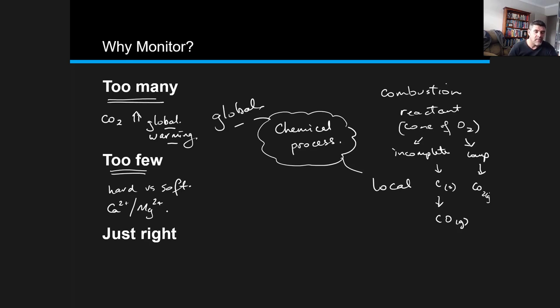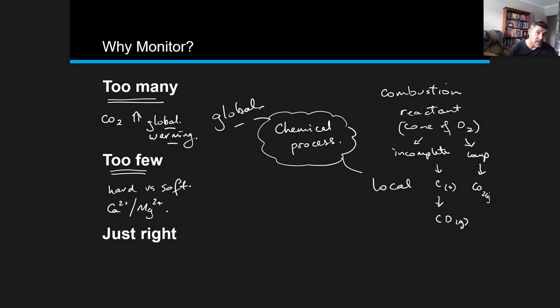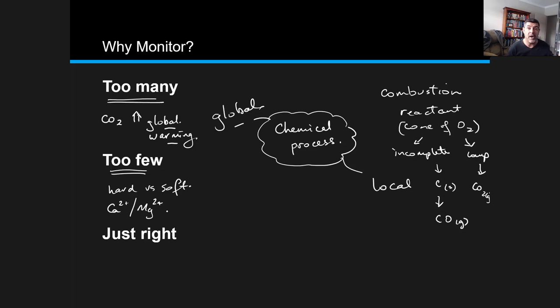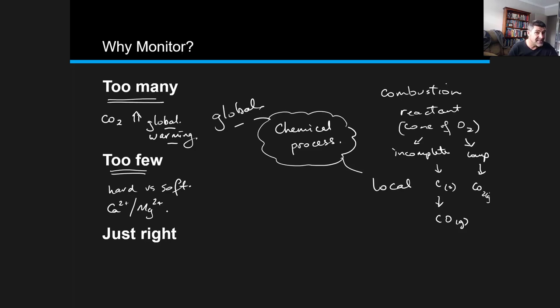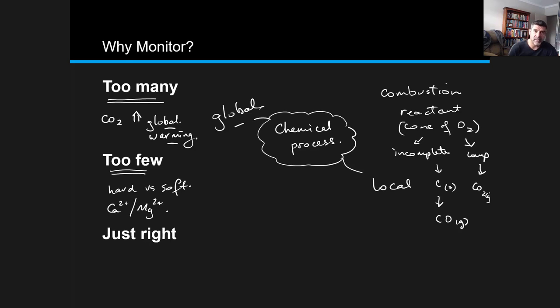However, if the concentration of these is too low, we can find that there can be some erosion - the water can actually start to eat away at the piping. Therefore, sometimes part of the process of water purification is the addition of calcium ions in order to raise that concentration of calcium and reduce the prospects of damage being done further down the line. So there are problems occasionally with too much and problems also with too few.